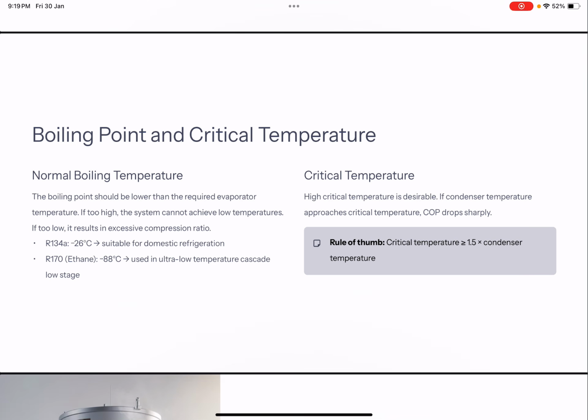The second important thermodynamic property is what is known as the critical temperature. Critical temperature is the temperature at the peak of the vapor dome, where the latent heat of vaporization becomes zero. So, if the critical temperature is lower, then the condensation would be closer to the critical temperature, and if the condensation is closer to the critical temperature, the performance would drop sharply. This you can understand by drawing the vapor compression refrigeration cycle on a pressure enthalpy diagram.